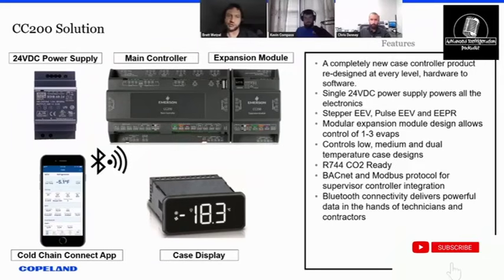Are we sharing a pressure transducer for this, or do they have each individual? That's a good question. We can do it both ways. There's a parameter in there where you select, is it one per case or one per coil? Okay. I've seen it done both ways, so we support it both ways.